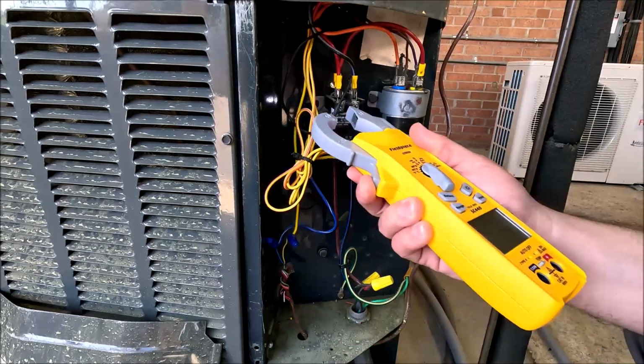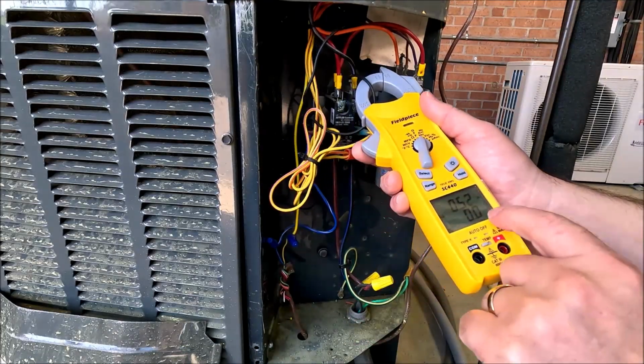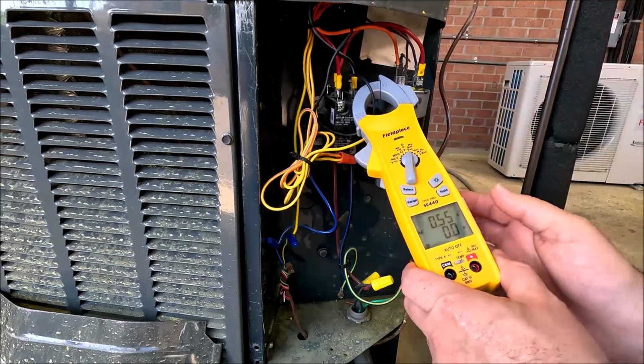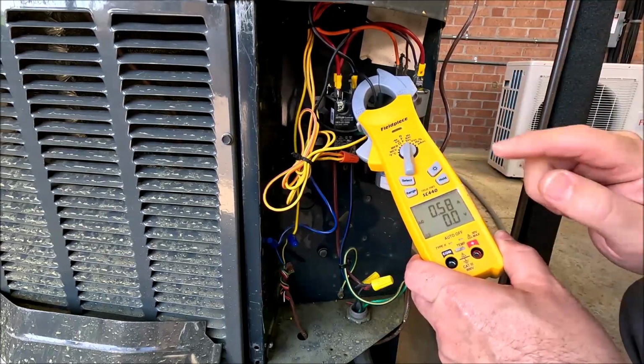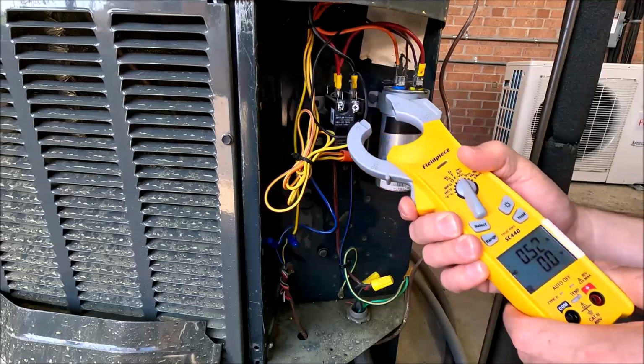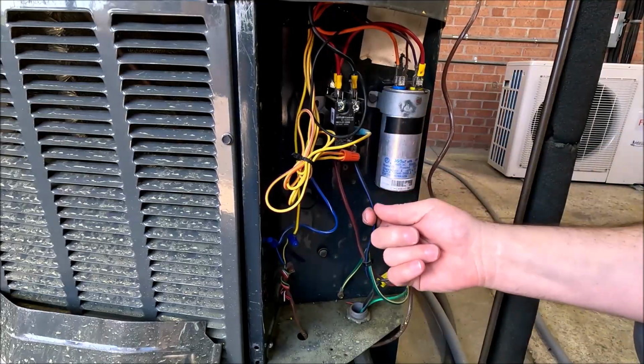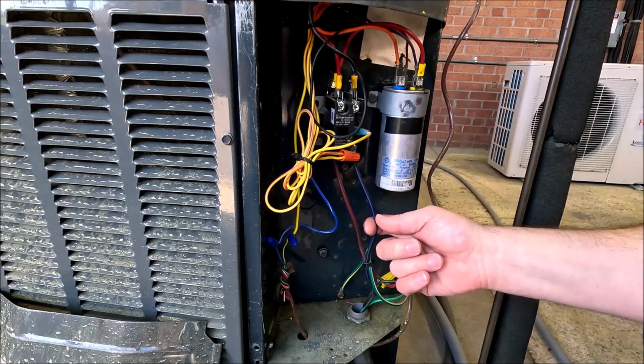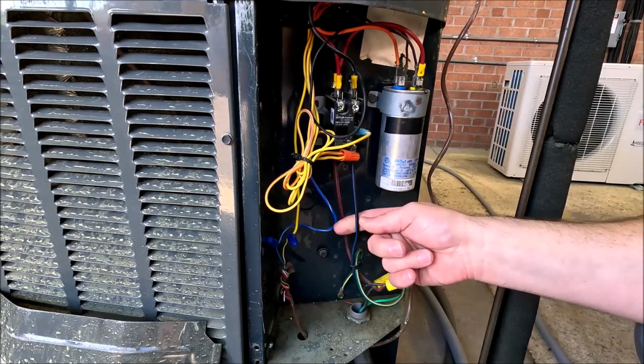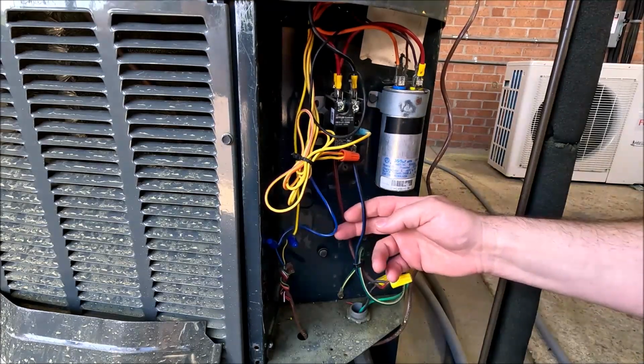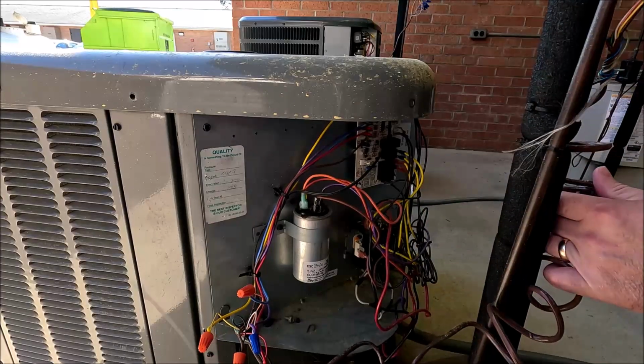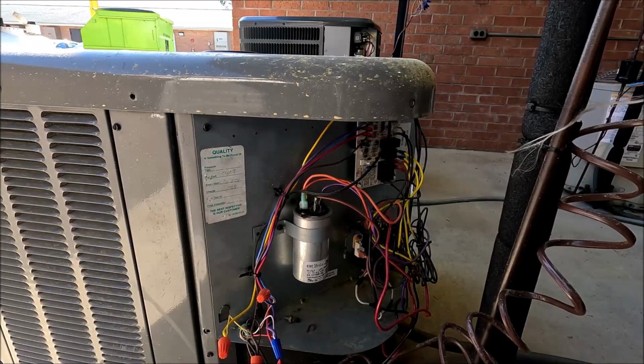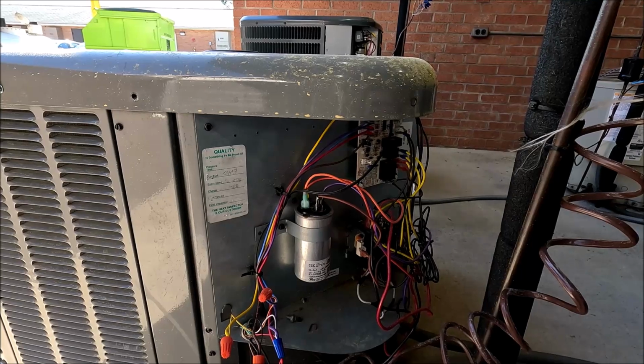So by me being able to clamp on the common side or the L2 side of the outdoor fan motor, I know that that's about a 1/2 amp. So of that 5.5 amps, 5 is going to be the compressor and a 1/2 of it's going to be the outdoor fan. And that's pretty much the only 2 loads we have out here. Then we get the good old heat pumps, and it's the same concept.